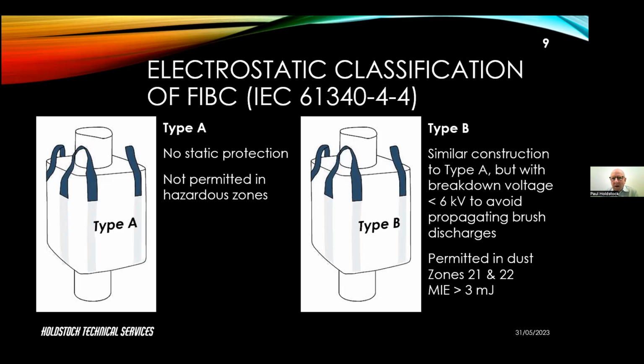Now, in theory, but not in practice, brush discharges can ignite combustible dusts with an ignition energy less than 3 millijoule. That's in theory. It's never been shown in practice, but theoretically, a brush discharge could ignite a dust with an ignition energy less than 3 millijoule. So the requirement is that you can use these provided the minimum ignition energy is greater than 3 millijoule.